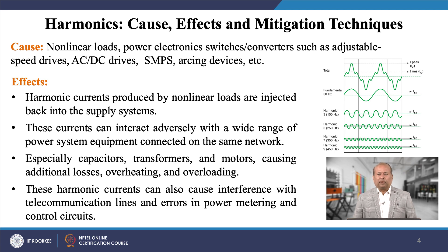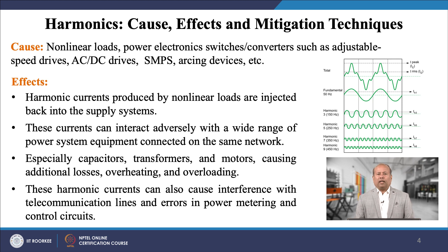You can see an example in the given figure. The fundamental component of current is at 50 Hz, and subsequent harmonic components of the 3rd, 5th, 7th, and 11th are also present. The resultant current waveform is distorted. For the sake of understanding, if we take a square wave it will produce close to 48.3 percent deviation from the ideal sinusoidal waveform — that is THD equal to 48.3 percent.